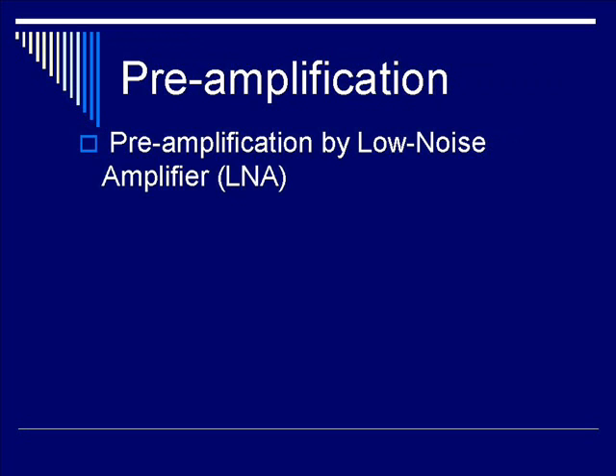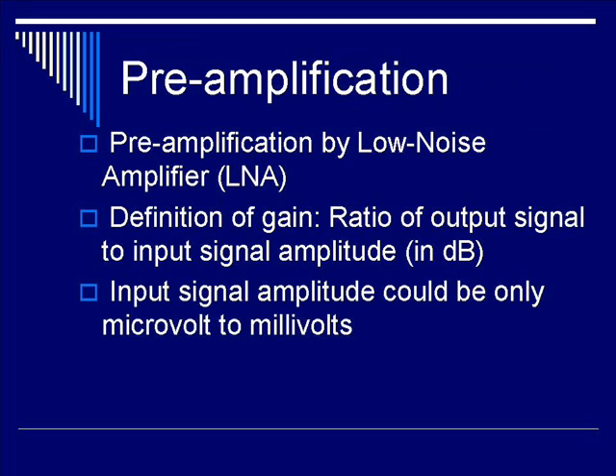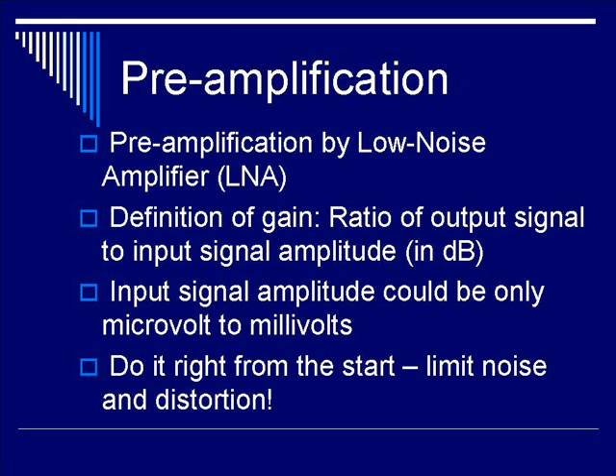The ultrasound echoes that return from the transducer are amplified with a low noise amplifier, otherwise known as LNA. The definition of gain through the LNA is the ratio of the output signal to the input signal in units of decibels, dB. The input signal amplitude is oftentimes very small, ranging from microvolts to millivolts. Therefore, by amplifying from microvolts to millivolt levels, it is important — aside from getting the desired amplitude — to limit the noise and distortion, because all of those things get amplified as well in later stages.